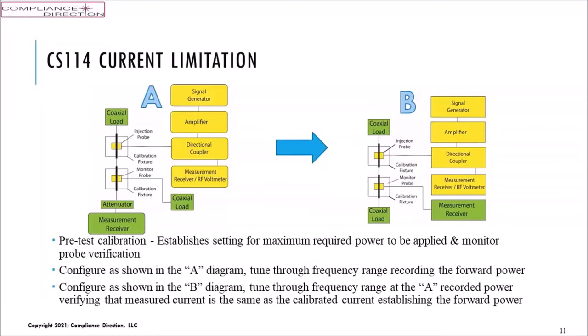Now, that checks our settings, our power levels that produce the calibration current. Calibration current is a current that's different from the test current, and some of that is related to the fact that the coaxial load and measurement receiver puts a 100 ohm circuit, or current loop, into 100 ohms. So when test comes about, we always test 6 dB higher to simulate the 50 ohm cable. And we test at 6 dB higher than the most current limit that we would have.